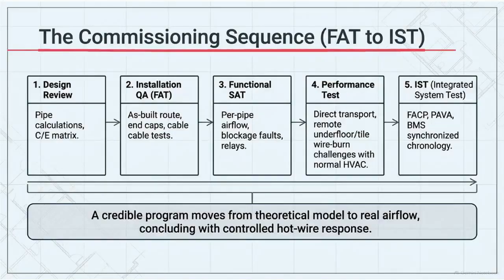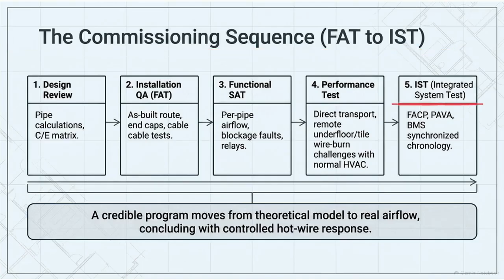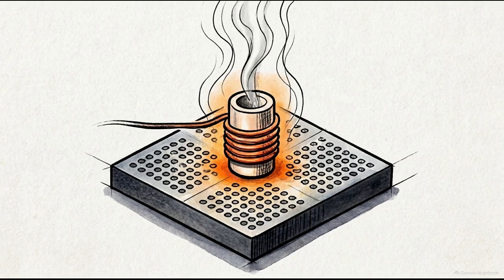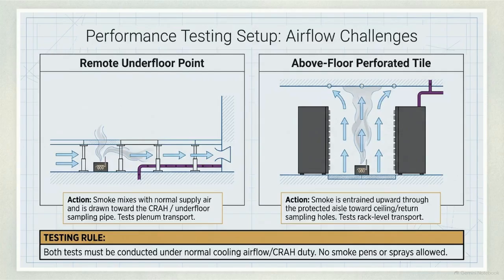Proving the system requires a 5-step commissioning sequence that moves from theoretical OEM pipe models to full integrated system proof. The central performance proof is the hot wire burn test. This must be conducted under normal data center cooling airflow. Smoke pens and sprays are not permitted. Engineers use 2 mandatory challenge points.